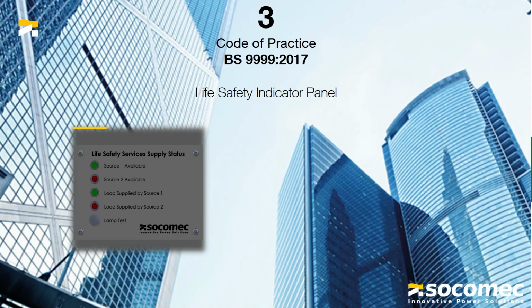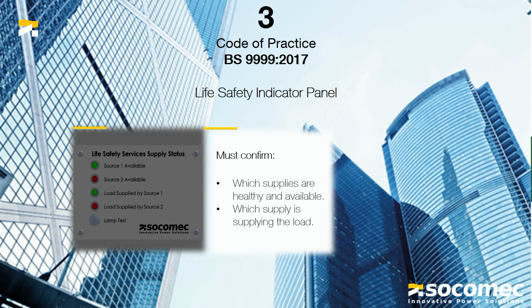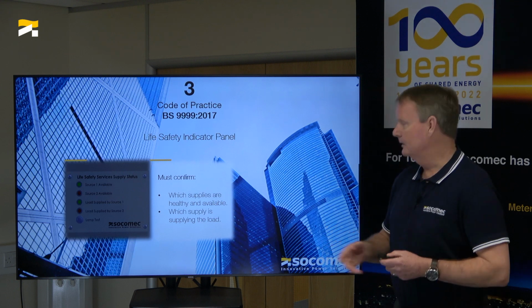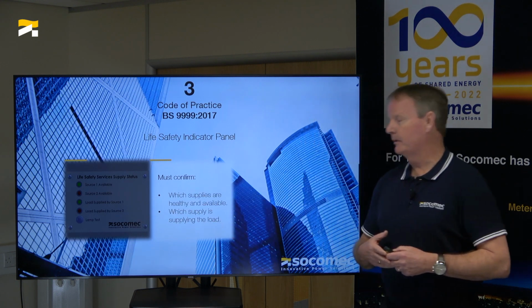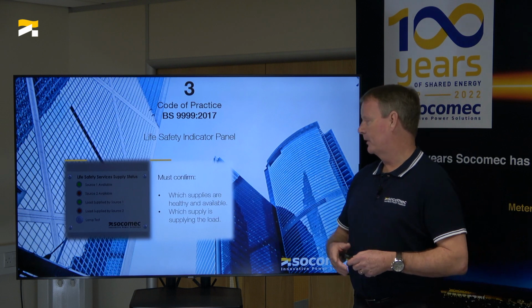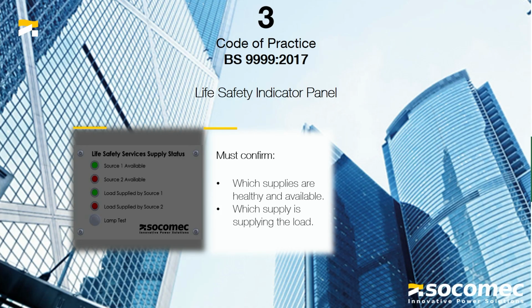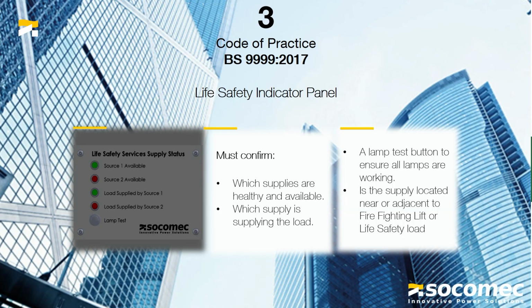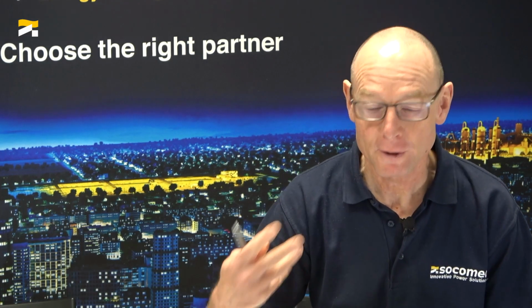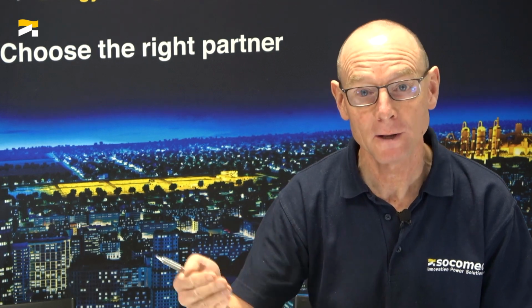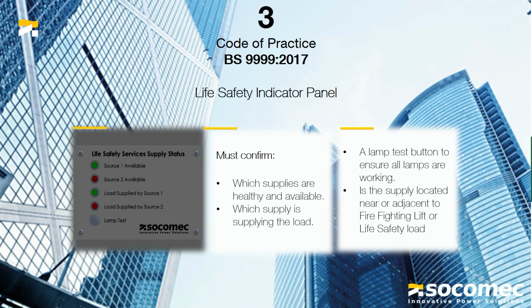One of the parts also references the life safety indicator panel. Architects don't really like them because they have a nice foyer, marble, looks beautiful, and then somewhere in the middle is a life safety services supply status, which tells them which supplies are healthy and available, and which is supplying the load. You basically get 4 indicators to show whether the source is available and which is actually supplying the load. You have to provide that information, plus a lamp test button so firefighters can ensure the lights are actually working.